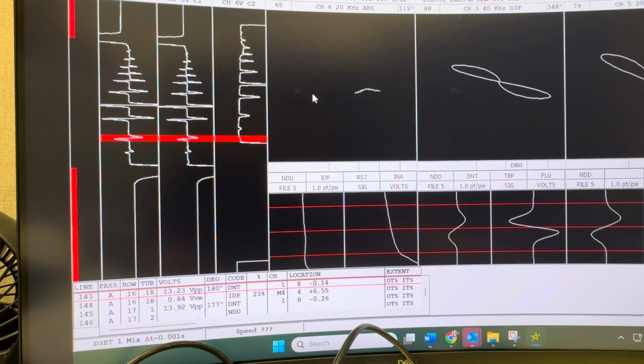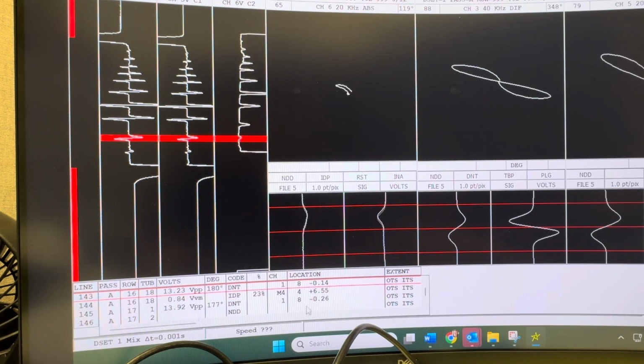Now, the way the bobbin coil is, if that's all you have is the pair of coils, you would actually want to reset that to 0, but I'm going to manually reset it so you can see how that's done again. You do the shift middle button and you just drag it right about there. That looks like they're lined up pretty good, right? Now, how would you do data slewing with rotating coil data, and why would you want to do that? Well, like I said, if you have a single coil rotating coil, you don't need it.